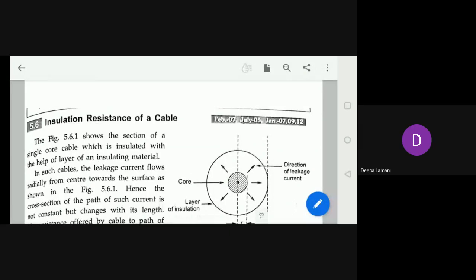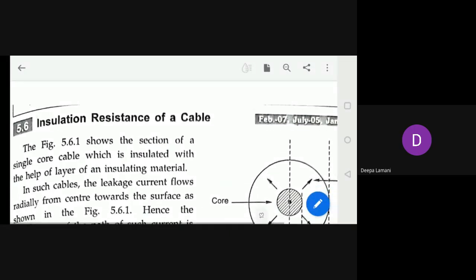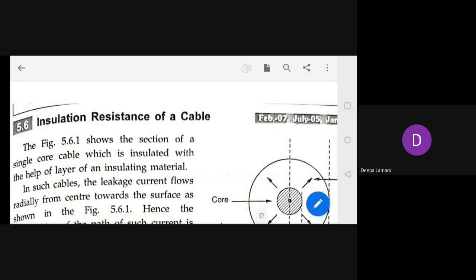The next topic is insulation resistance of a cable. Insulation resistance refers to how much resistance the insulation outside the core provides to the current — layer by layer, how much resistance is provided to the path of leakage current. In single core cables, the leakage current flows radially, and the cross-section of the path for such current is not constant.